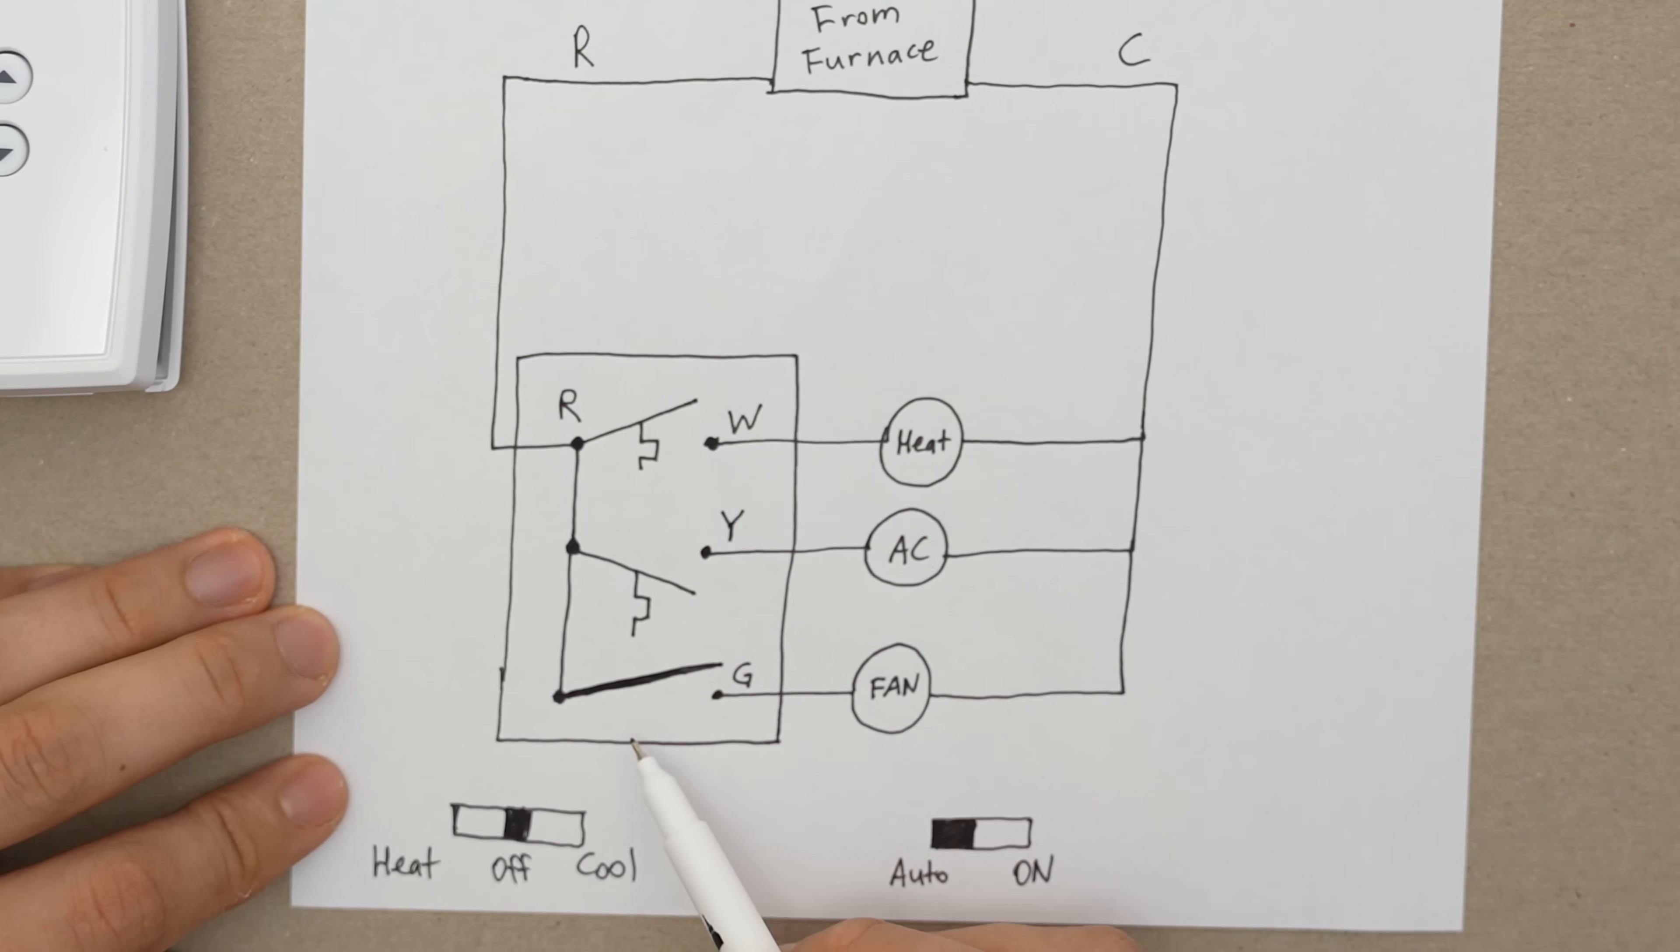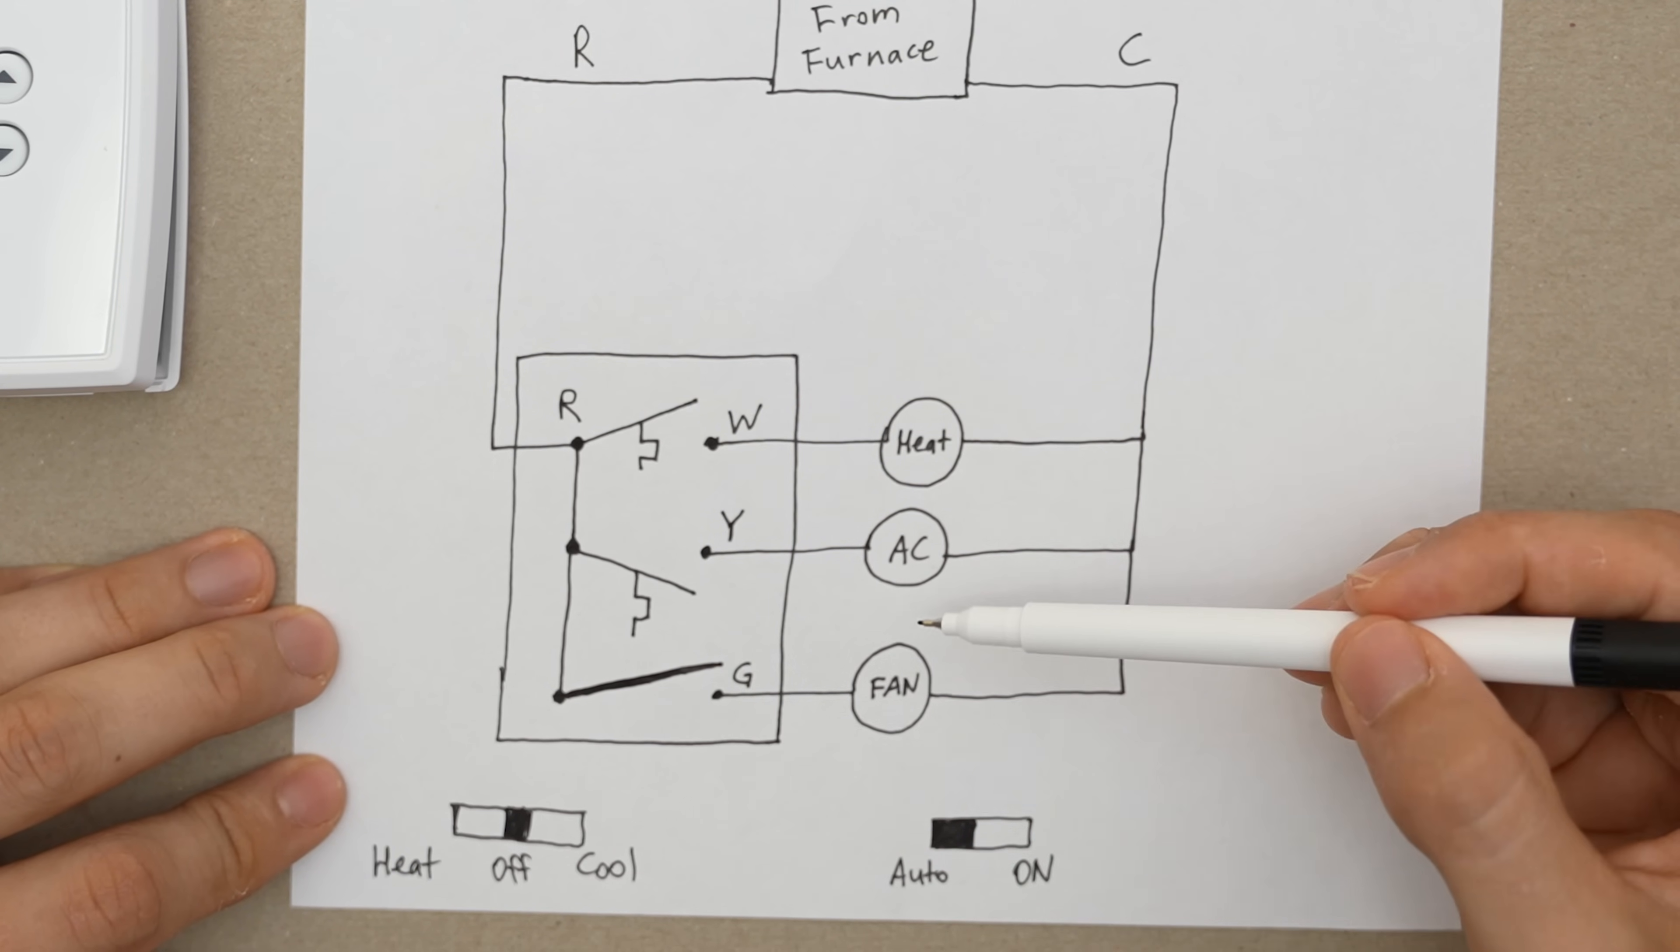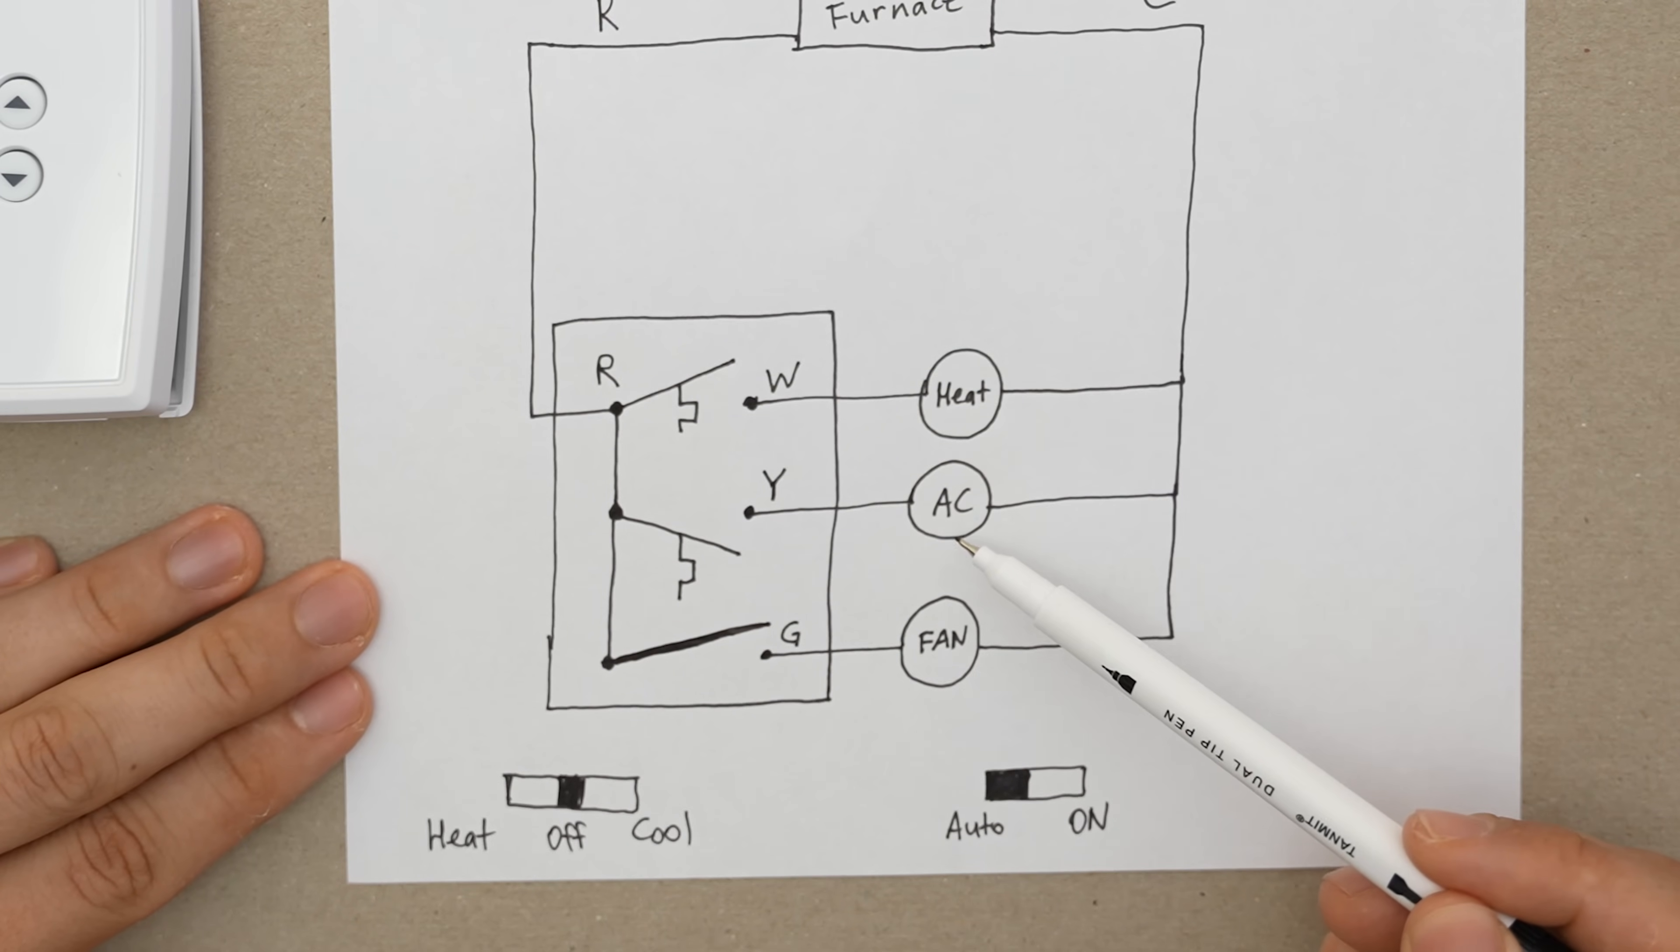And the last switch that we have is for the fan. And this is just a basic switch. It's almost like a light switch. It's either on or off, except in our case, it's either auto or on. When it's in automatic, that means that whenever the heat comes on, whenever the furnace comes on, the fan will come on. Whenever the air conditioner comes on, the fan will come on as well. And that is controlled by the control board in the furnace. When we switch this switch to on, that simply means that power will be going to the fan all the time. So the fan will be running literally 24-7, regardless of whether the heat or the AC is running or not.